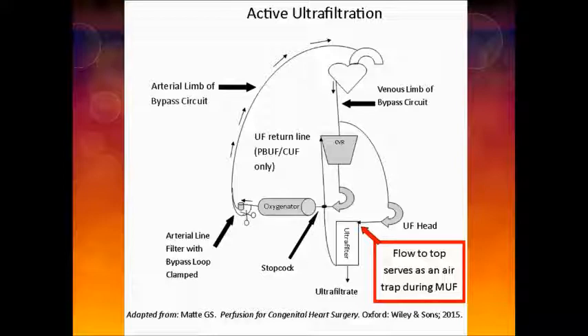This setup for MUF is a variation of the technique described by the Halifax, Nova Scotia group back in the year 2000. To note, with this arrangement, there is no possibility of pulling air across the hollow fiber membrane oxygenator. Any negative pressure would be exerted on the venous line. It would therefore pull from the venous flow or from the reservoir through the venous connection. Using this arrangement allows one to utilize a single, consistent method of active ultrafiltration throughout the case without relying on system pressure or worrying about the difficult to quantify shunt, as with passive ultrafiltration. And during MUF, I believe it is safer.